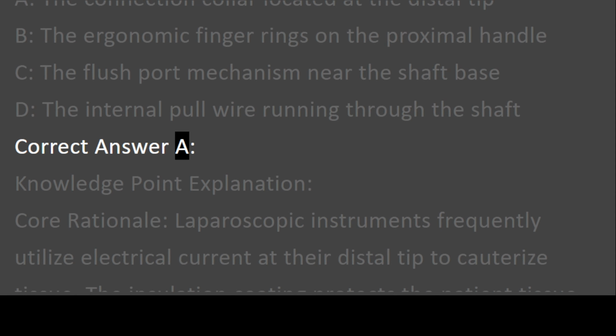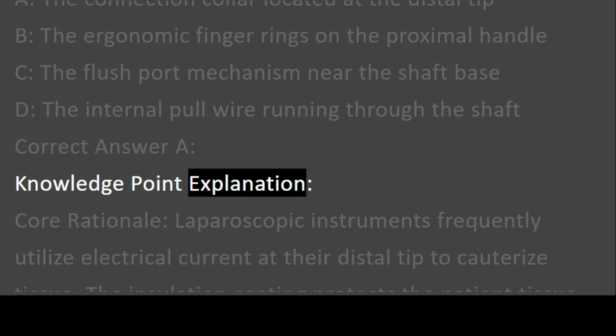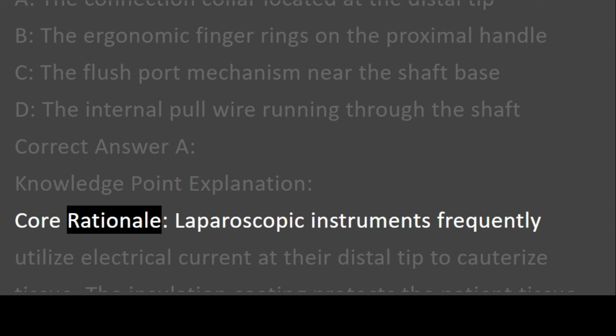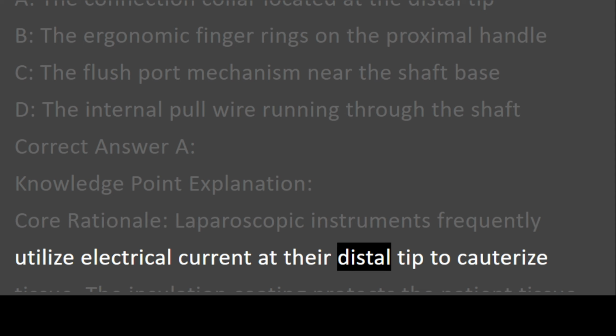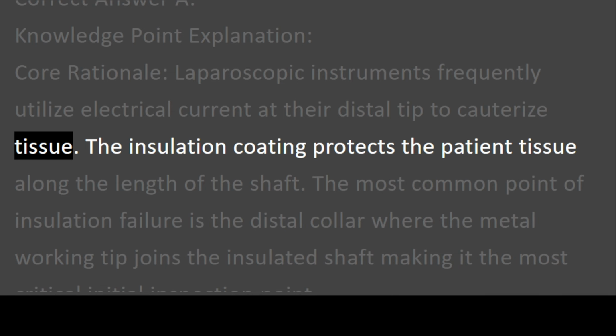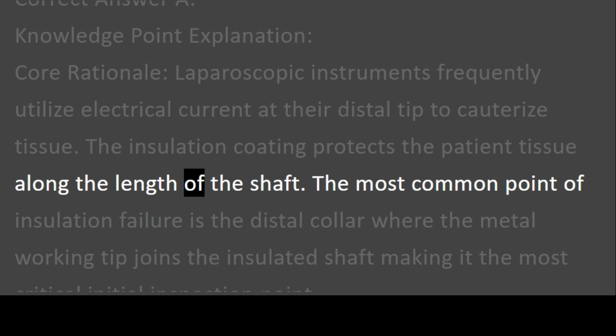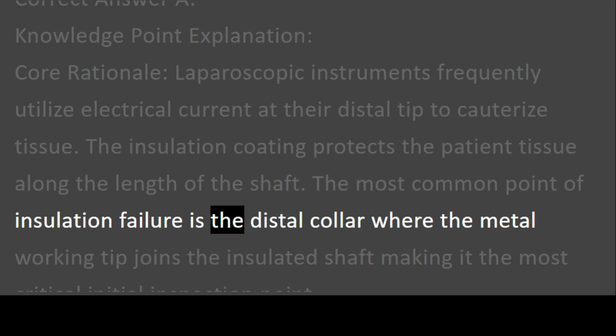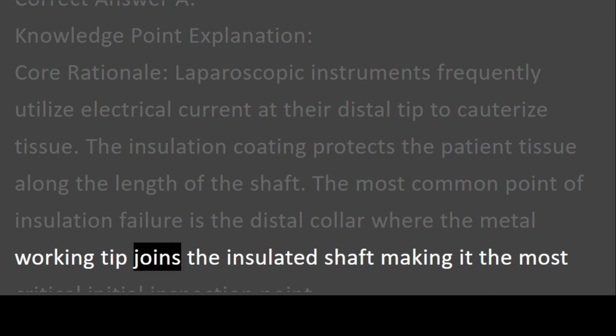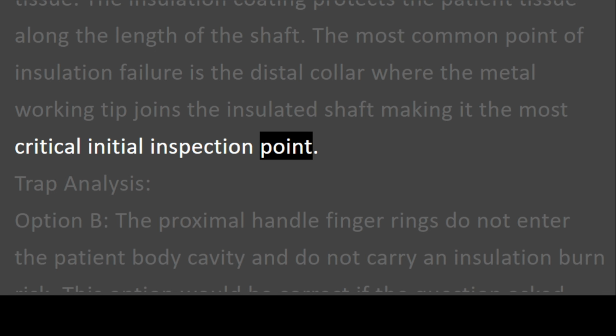Correct answer A. Knowledge point explanation. Core rationale. Laparoscopic instruments frequently utilize electrical current at their distal tip to cauterize tissue. The insulation coating protects the patient tissue along the length of the shaft. The most common point of insulation failure is the distal collar, where the metal working tip joins the insulated shaft, making it the most critical initial inspection point.